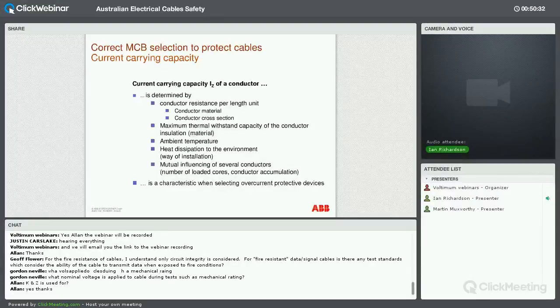The current carrying capacity of a cable or a conductor, a variety of factors will come into this. The conductor resistance, of course, depends on the type of material and the conductor cross-section. The thermal withstand depends upon the type of insulation material that surrounds the conductors. We also consider the ambient temperature, how the heat can be dissipated into the environment, which will then depend on how hot the cable actually runs. And then you've got your installation methods, and you'd be very familiar, of course, with the requirements in AS3008 and such, where if you bundle cables together, or if they're standing in free air or buried in conduit and so on and so forth, you've got varying current carrying capacities of these cables depending on the installation method which is employed.